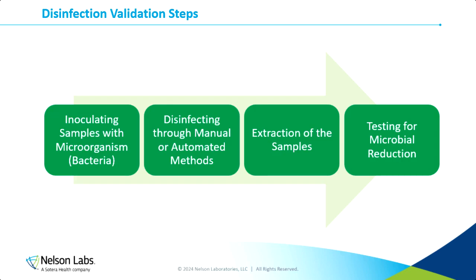Just as a quick overview of how a disinfection validation is performed, the first step in the process is that the device is inoculated with the challenge microorganism, and the microorganisms that are chosen will be based on the disinfection level that you are trying to achieve. After the samples are inoculated, they are taken through the disinfection process, whether that be manual or automated, whatever disinfection procedure you are trying to validate. They are then extracted in order to recover any microorganisms that may have survived the disinfection process, and then they are plated on appropriate agar, and those colonies are counted after incubation, and a log reduction is calculated.